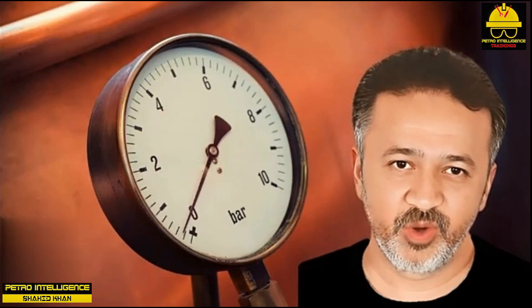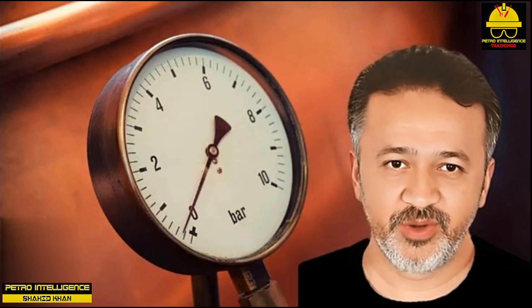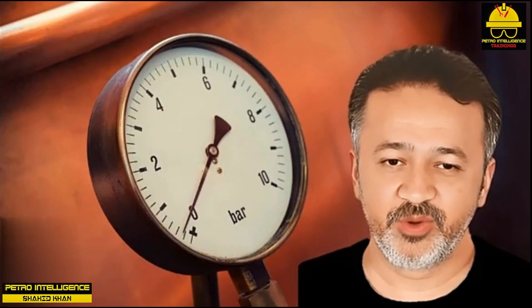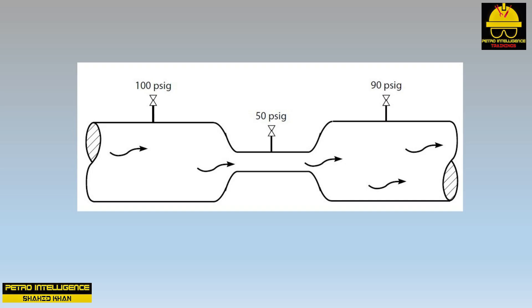The orifice flanges are kept close to the orifice plate because when liquid velocity decreases downstream, pressure partly recovers — this is called pressure recovery. Whenever the velocity of a flowing fluid decreases, its pressure goes partly back up; an extreme example is water hammer. The pressure at the end of the pipe is lower than at the inlet due to frictional losses. The orifice coefficient K accounts for both frictional pressure losses and conversion of pressure to velocity.